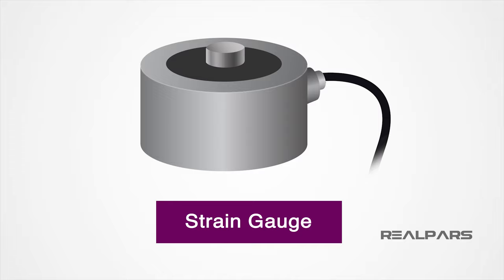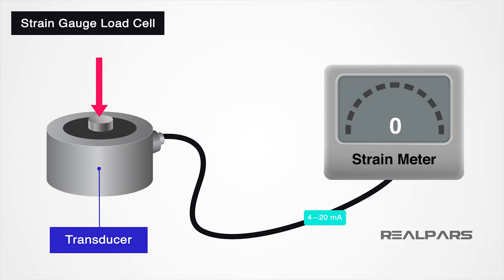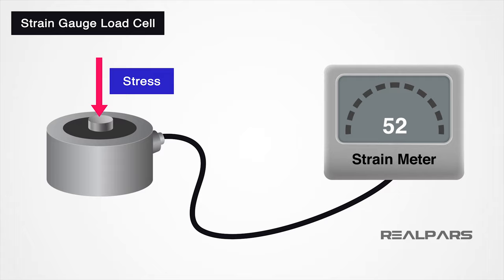The next type of load cell we will discuss is the strain gauge. This is the most popular style of the load cell. A strain gauge load cell is a transducer that changes in electrical resistance when under stress or strain. The electrical resistance is proportional to the stress or strain placed on the cell, making it easy to calibrate into an accurate measurement.